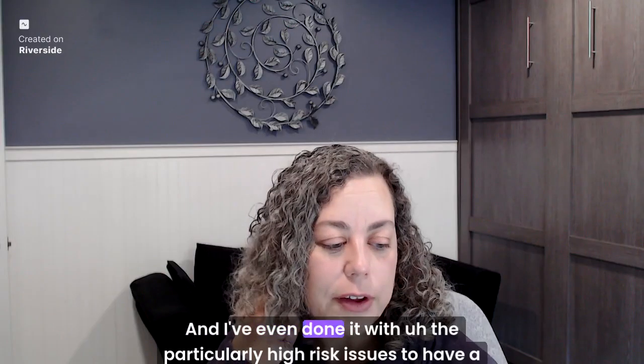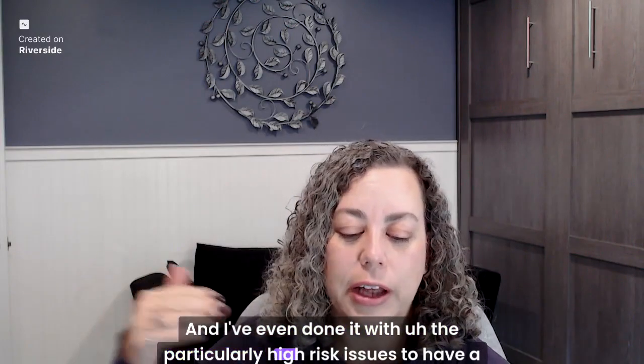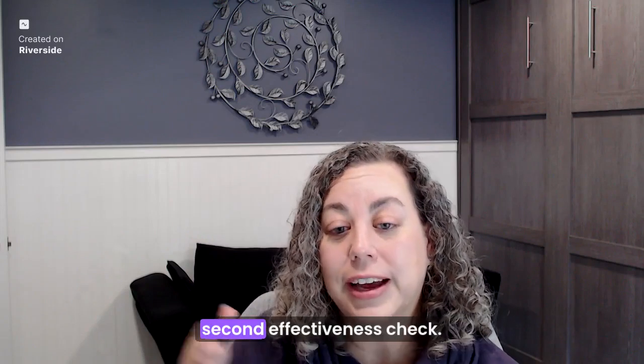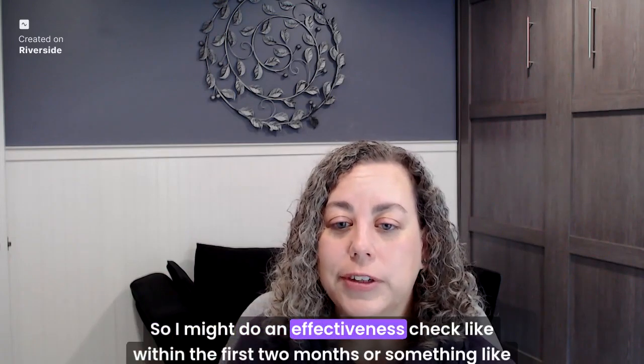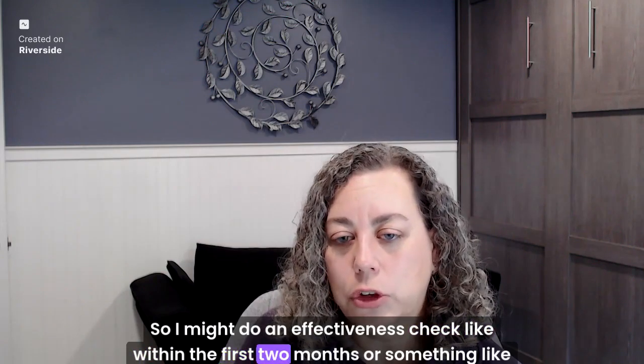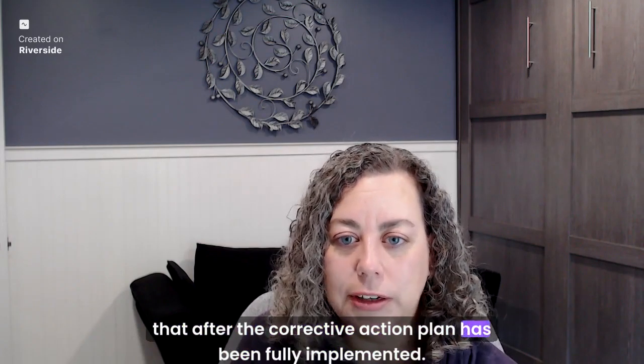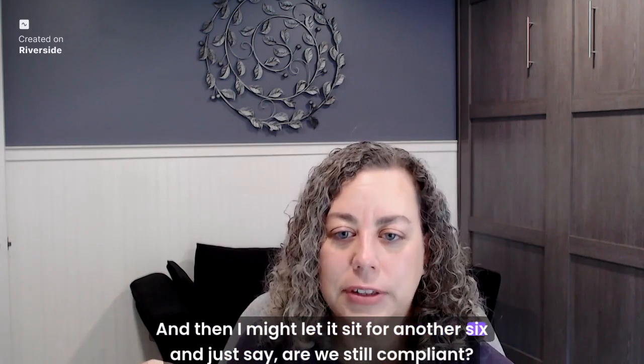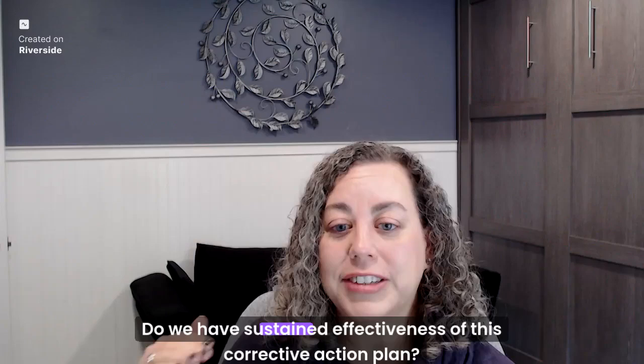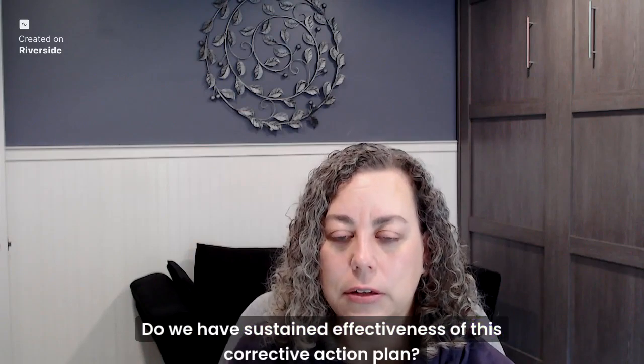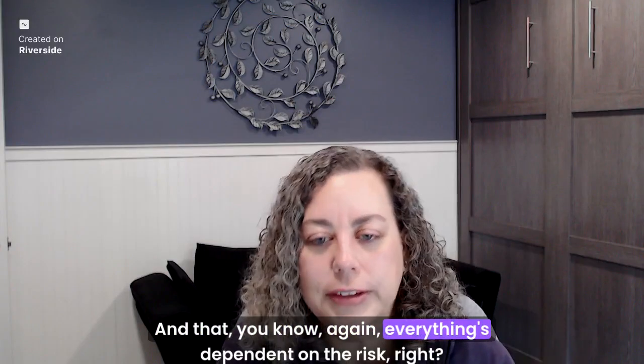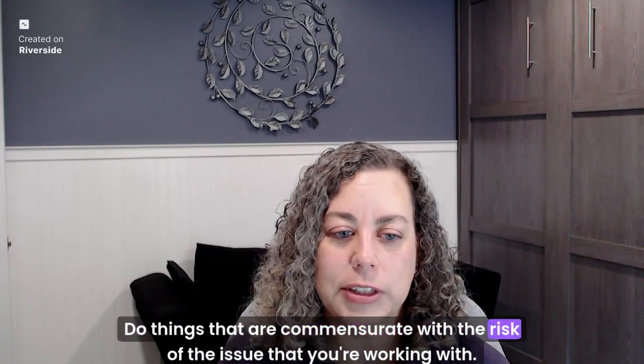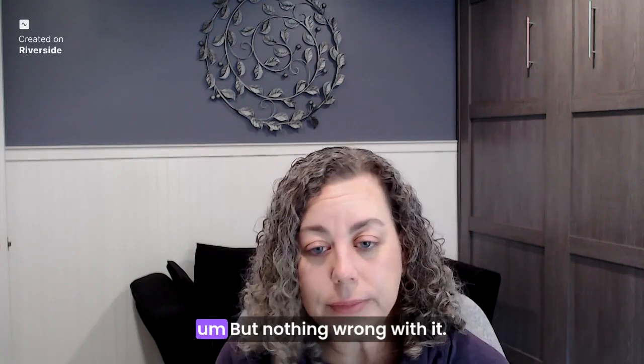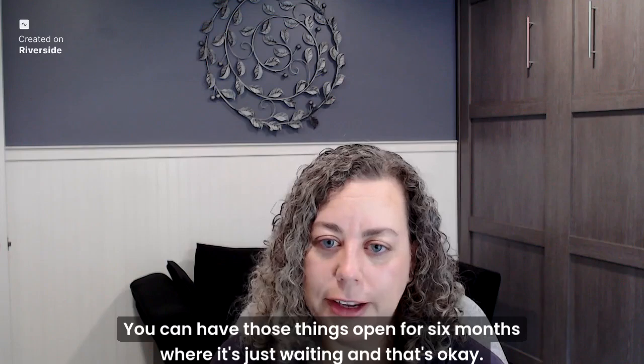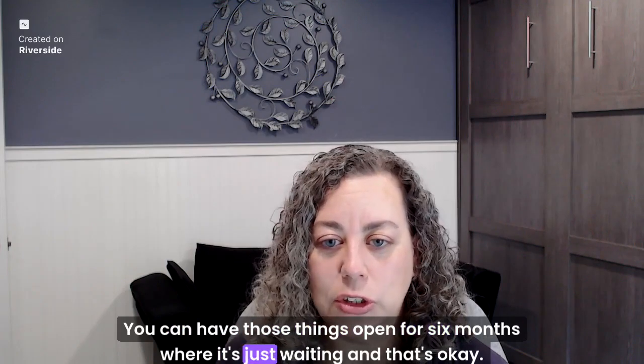Agreed. And I've even done it with particularly high risk issues to have a second effectiveness check. So I might do an effectiveness check within the first 2 months after the corrective action plan has been fully implemented. And then I might let it sit for another 6 and just say, are we still compliant? Do we have sustained effectiveness of this corrective action plan? Yeah, and again, everything's dependent on the risk, right? Do things commensurate with the risk of the issue you're working with. There's nothing wrong with it. You can have those things open for 6 months where it's just waiting, and that's okay.